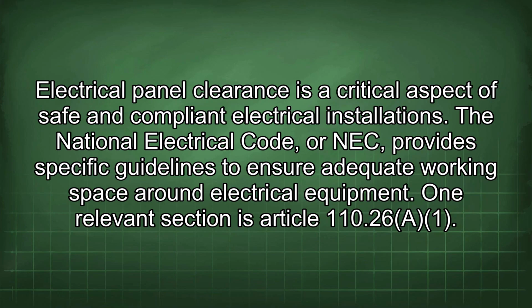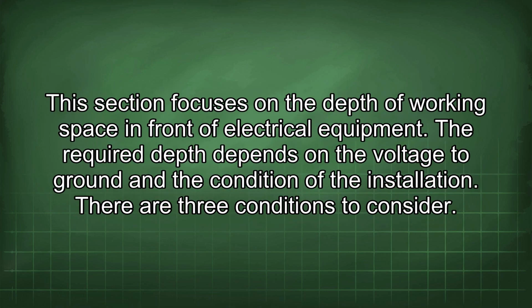Electrical panel clearance is a critical aspect of safe and compliant electrical installations. The National Electrical Code, or NEC, provides specific guidelines to ensure adequate working space around electrical equipment. One relevant section is Article 110.26(A). This section focuses on the depth of working space in front of electrical equipment. The required depth depends on the voltage to ground and the condition of the installation. There are 3 conditions to consider.